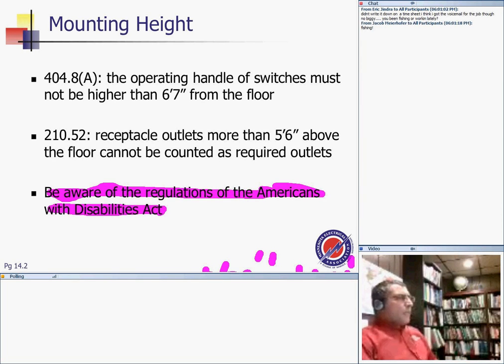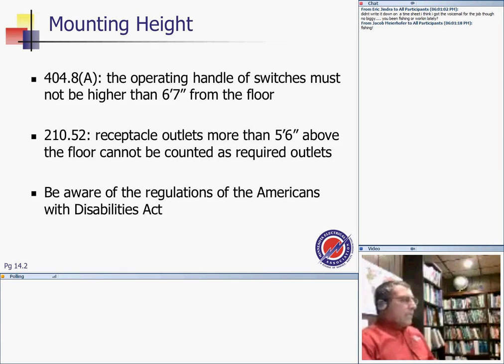Other than the Americans with Disabilities Act, let me ask you this, my friend: where in the code does it tell you how high you can put a receptacle off the finished floor? Is there anything in the code that tells you how high you can put a receptacle? How about an X for no, and a green check for yes? Anything in the code tell you how high you can put a receptacle above the finished floor, this limitation of you can't use it, in the NEC code book? Most people put them 12 inches off the finished floor. That's common. I mean, 12 inches off the finished floor, and you put your receptacle.